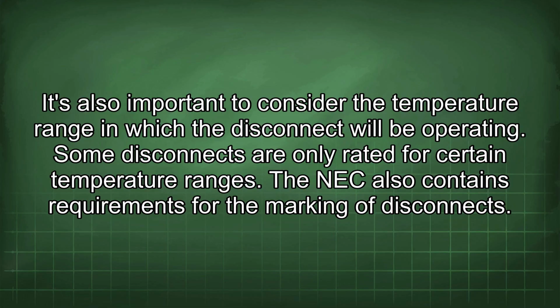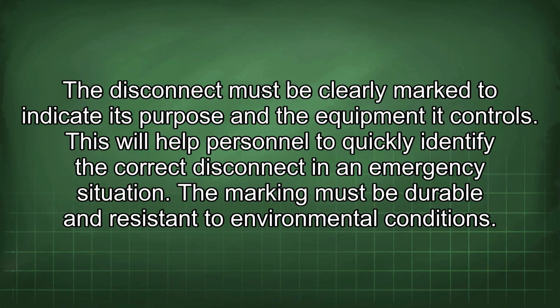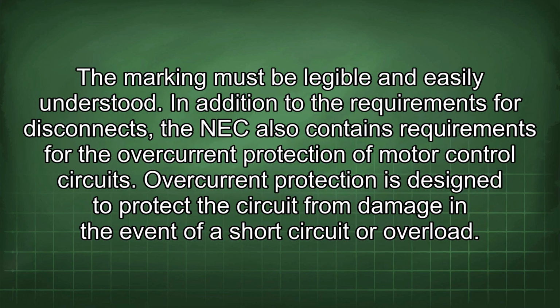The NEC also contains requirements for the marking of disconnects. The disconnect must be clearly marked to indicate its purpose and the equipment it controls. This will help personnel to quickly identify the correct disconnect in an emergency situation. The marking must be durable and resistant to environmental conditions. The marking must be legible and easily understood.